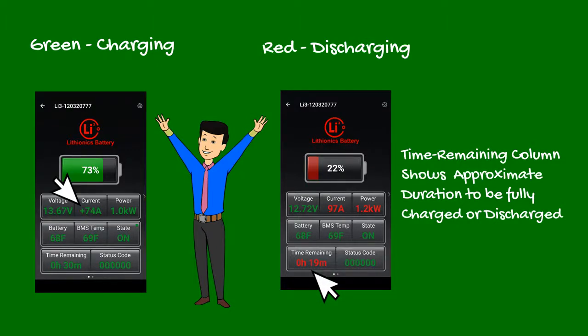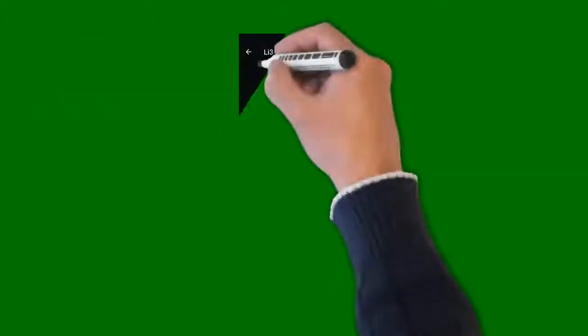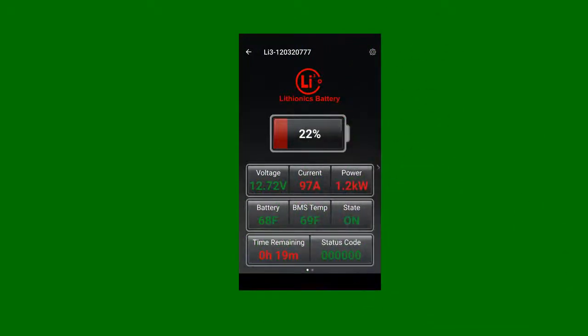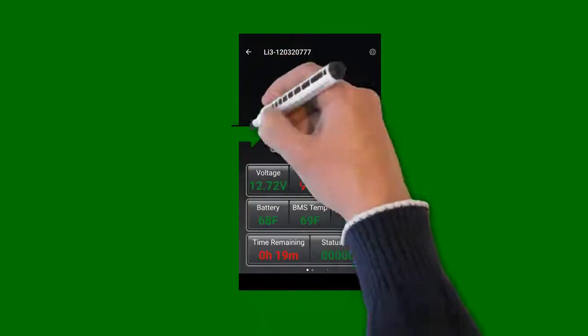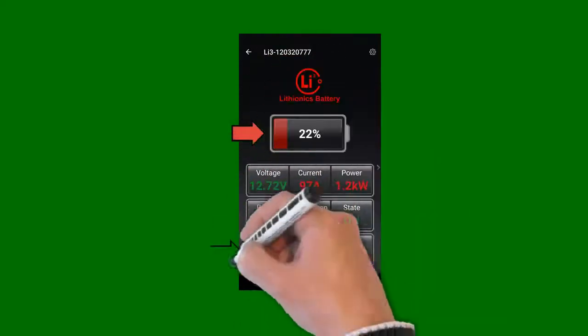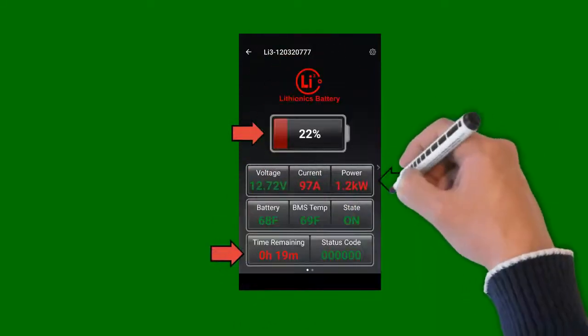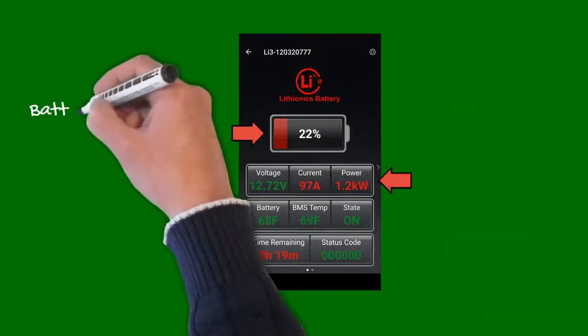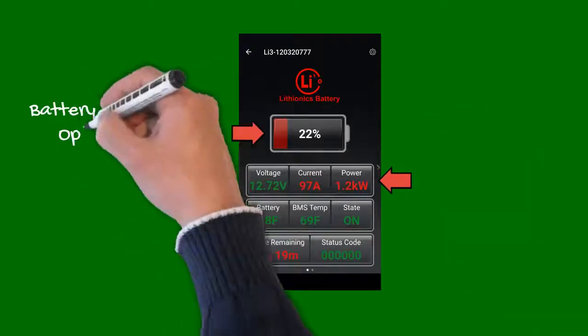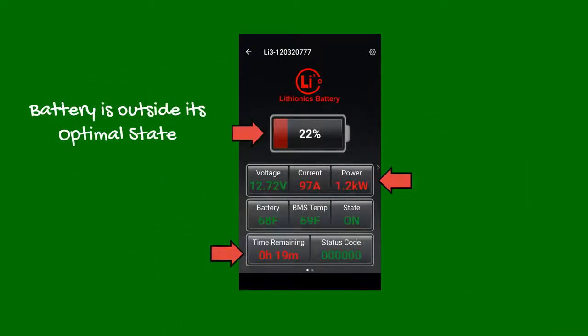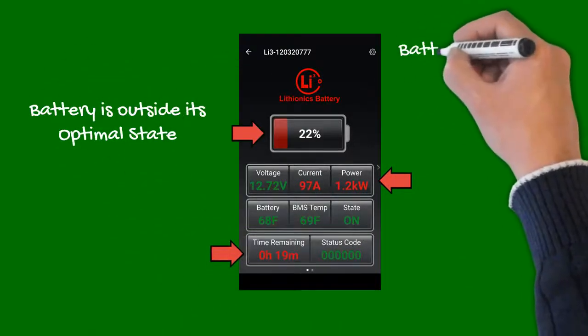The system's voltage, temperature, and state of charge values are also color-coded and indicate operating range of the battery. When these values turn red, it generally indicates the battery is outside of its optimal state, for example too hot or cold, or in the low voltage state and needs charging.